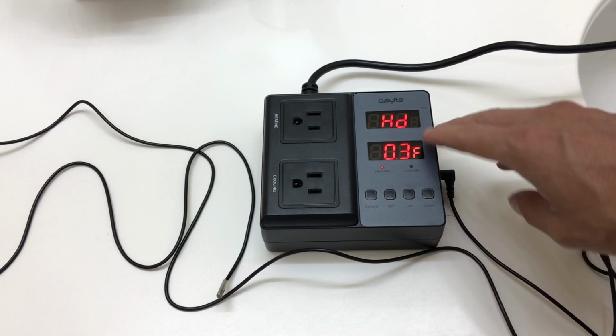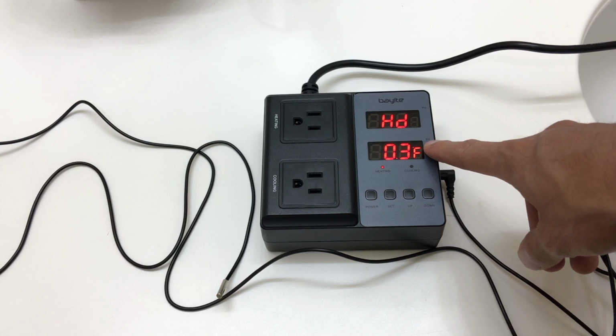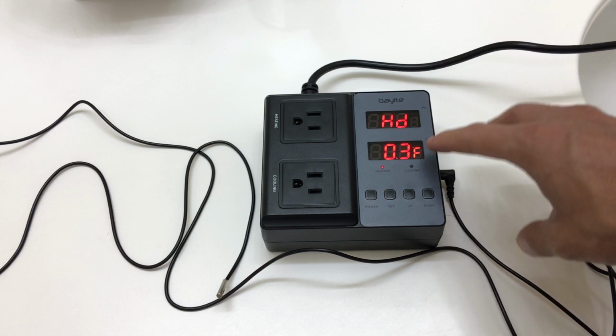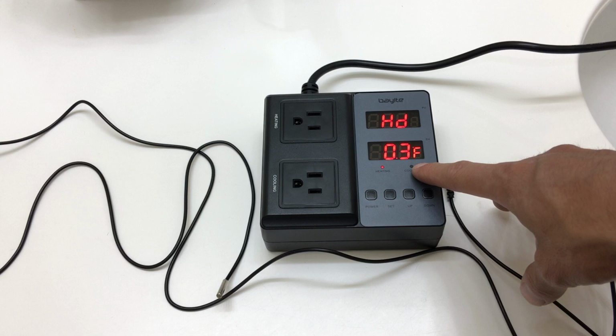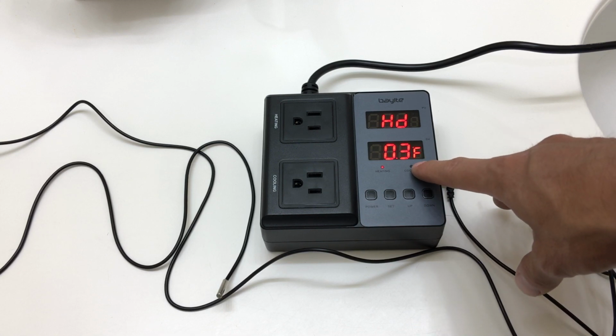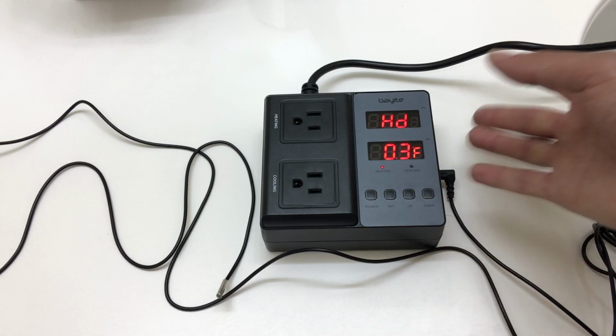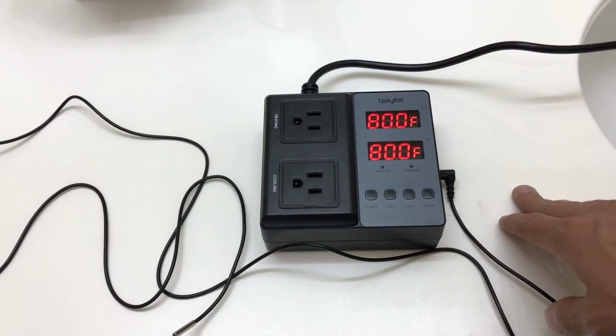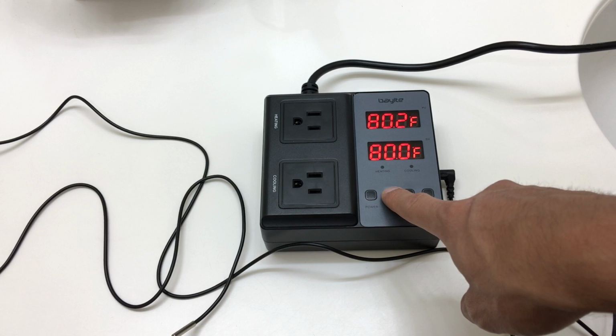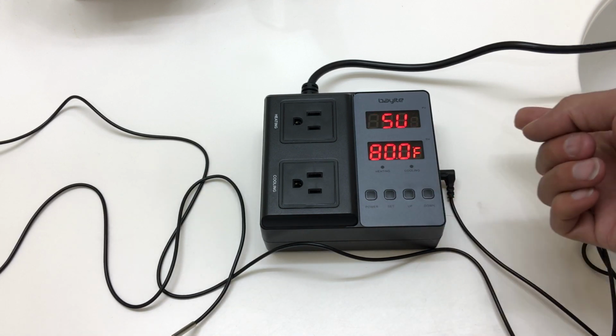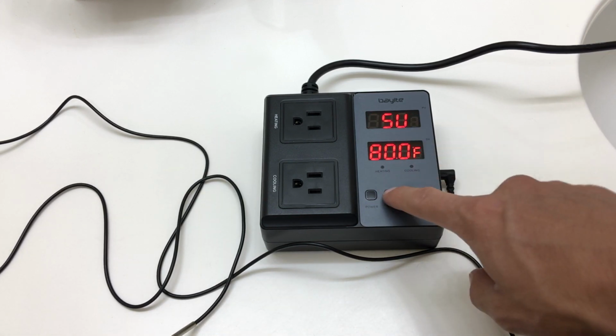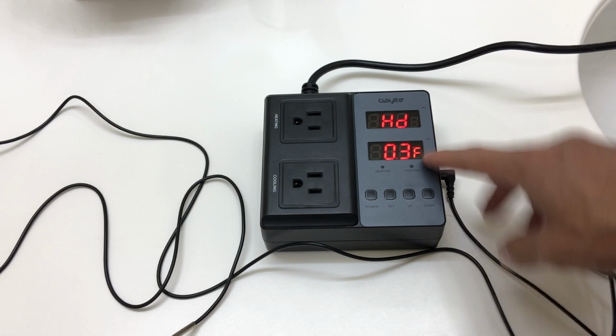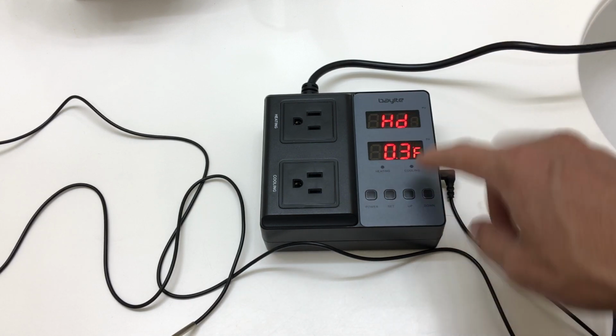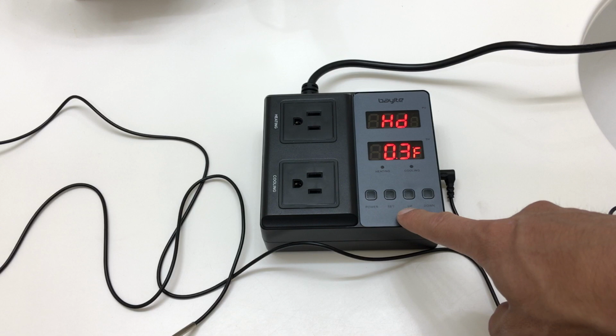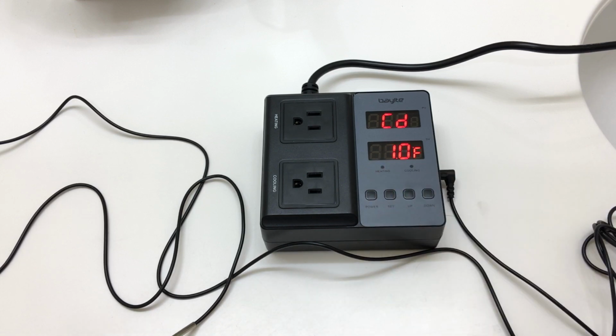So for the heating differential, 80 minus 0.3 is 79.8. When this reads 79.8, it's going to kick on the heater. It already exited the menu there, but it does save your settings - that was the heating differential menu.